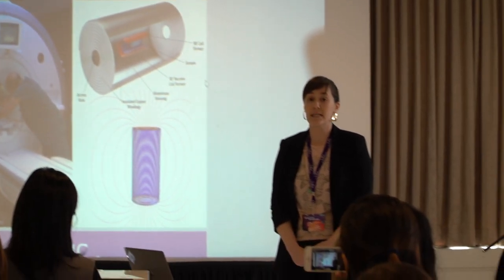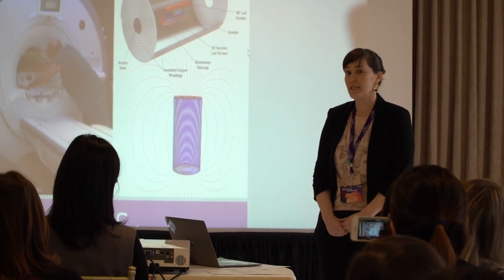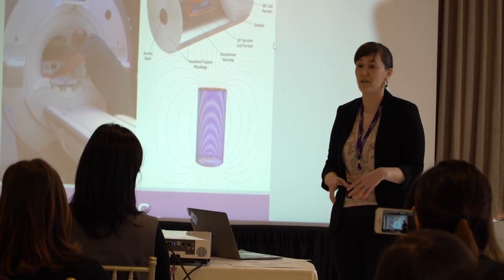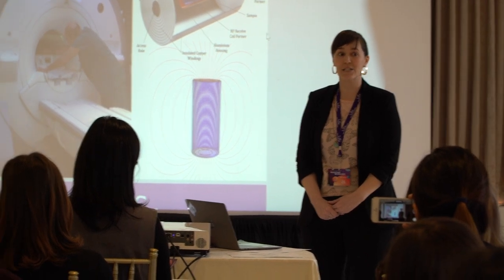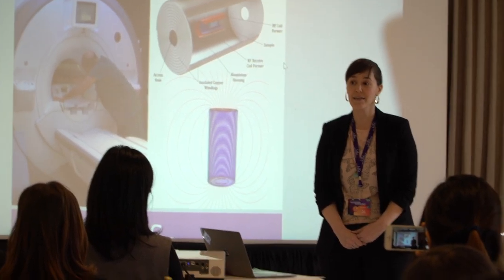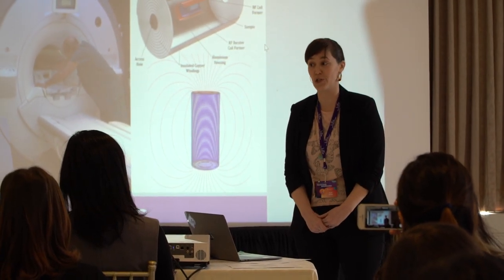This magnet is a cylindrical shape, and it has a field that's about 1,000 times weaker than the clinical MRI machines that you see today in a hospital. The magnet is also about 1 meter in length, and has a 50 centimeter diameter, so it is smaller, and it can't image humans.